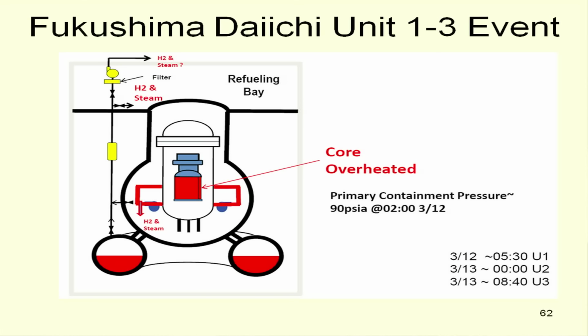and the reactor operators saw this. And so at some point, they have to make a decision. And they don't want the pressure vessel to just rupture. So they make a deliberate decision to start venting it out here into the dry well. And the venting, at the start, it's steam. But if the water level gets down, then you get a mixture of hydrogen and steam.